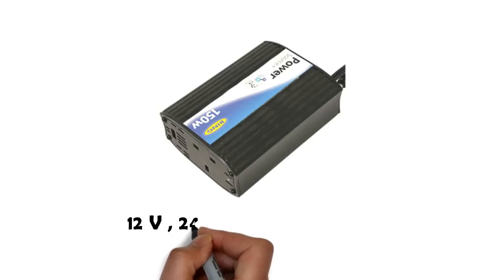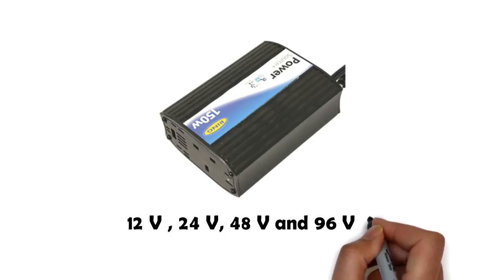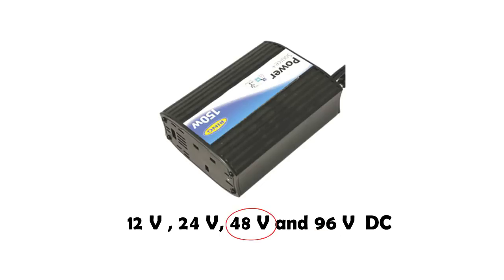That is, they can accept 12 volt DC, 24 volt DC, 48, or even 96 volt DC. Note that 48 volt DC input is the most common type of inverter used for residential solar PV systems, while 12 volt DC input inverters are more commonly used in portable applications.